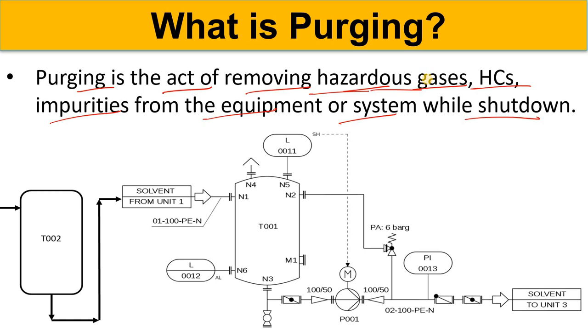Purging also helps to eliminate any combustible materials. You can simply say that it creates an inert environment. Now, which gas is used for purging? Most of the time you will see that nitrogen is used. As we discussed in our last videos, nitrogen is used as a purging medium. Air is also used, and sometimes steam is also used for purging — steam purging.